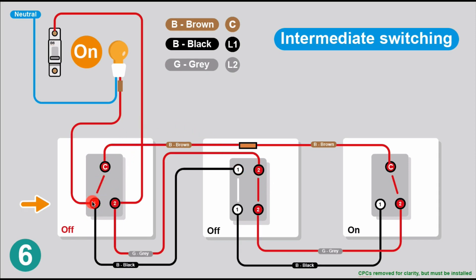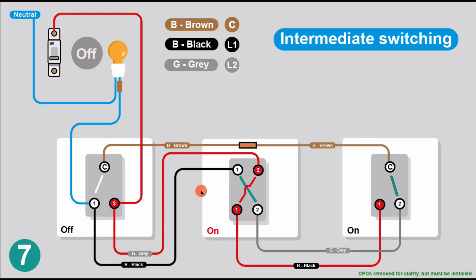Now we've switched the first switch off, so the configuration is off-off-on. There's no connection to common going one way, so power can only go the other way. Power comes around through the two-way switch, through the two-way switch, back through, and onto the light - the light is on. The next configuration is off-on-on. Following the power, it can't get that way; through the intermediate it crosses over, but can't get through the final connection. The light is not going to be on.